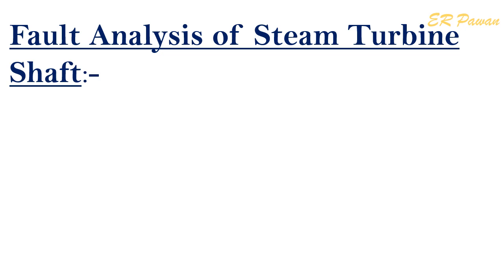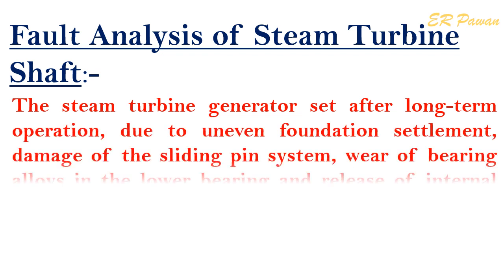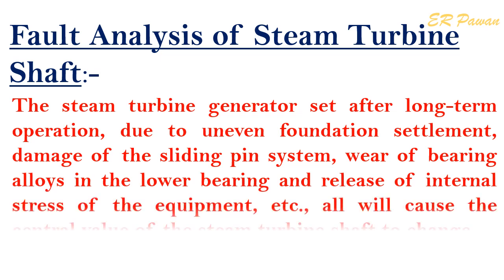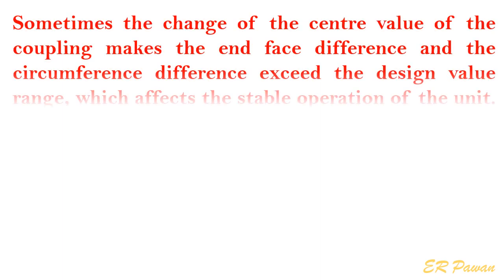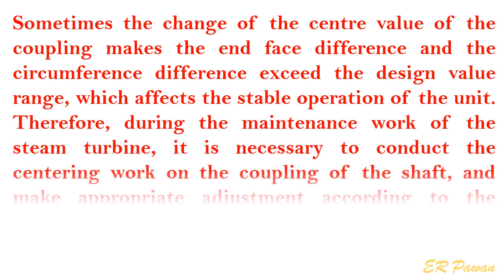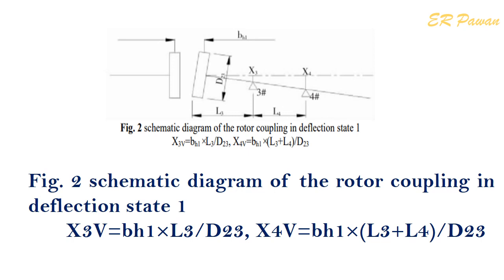Fault analysis of steam turbine shaft: After long-term operation, due to uneven foundation settlement, damage of the sliding pin system, wear of bearing alloys in the lower bearing, and release of internal stress of the equipment, the central value of the steam turbine shaft will change. Sometimes the change of the center value of the coupling makes the end-face difference and the circumference difference exceed the design value range, which affects the stable operation of the unit. Therefore, during maintenance, it is necessary to conduct centering work on the coupling of the shaft and make appropriate adjustments so that the center value deviation is within the design value range. There are three main cases in which the rotor coupling is deflected. As shown in Fig. 2, the center line of the rotor is not in a straight line, but the centers of the two back wheels just coincide.